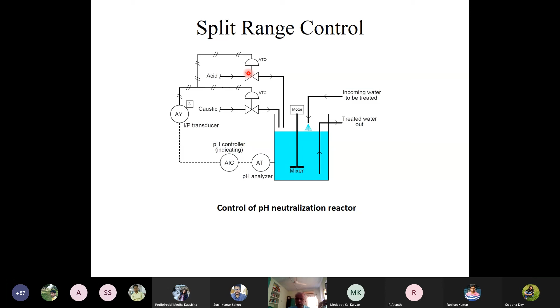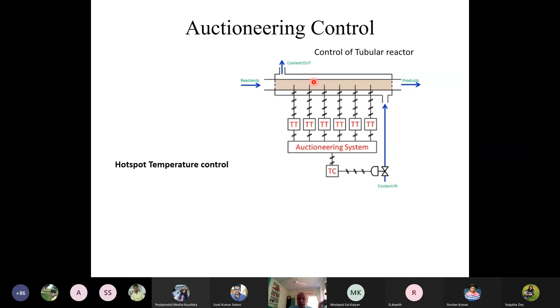Another important control strategy is the auctioneering control. In the auctioneering control, if you look at this control strategy of a tubular reactor, and we are controlling the temperature of the tubular reactor, normally if an exothermic reaction is taking place in this tubular reactor, there will be a situation of hotspots forming in some places in the reactor. And these hotspots are very difficult to locate because this is varying. If you have to control the hotspot temperature, then we have to find out the location of the hotspot. And this location normally travels through the reactor, which means it's very, very difficult to pinpoint where the hotspot locations are.